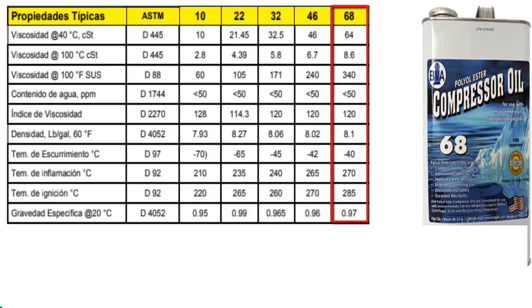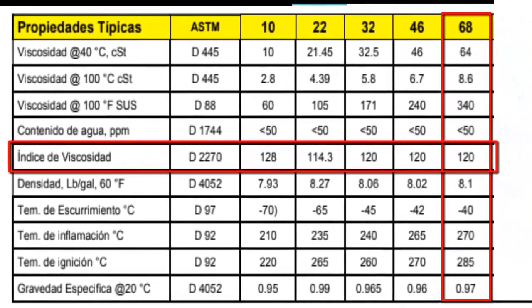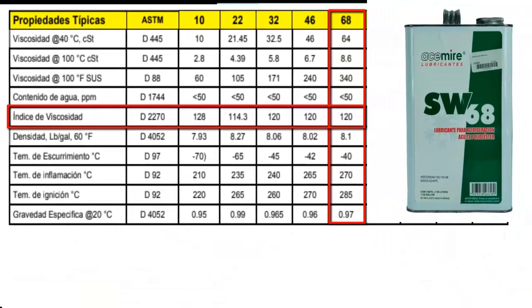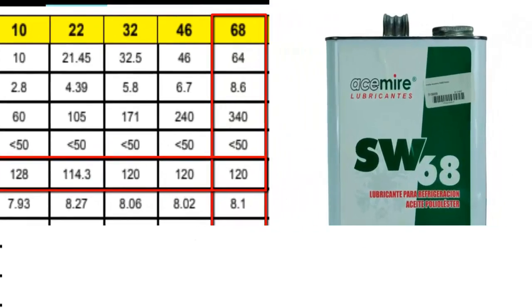The viscosity stability index is a numerical measure that describes how the viscosity of a lubricating oil varies with changes in temperature. When a lubricating oil has a viscosity index of 100, it is considered to have very stable viscosity over a wide range of temperatures. As the viscosity index decreases below 100, it indicates that the oil's viscosity tends to change more significantly with temperature variations. In this case, according to the table, this POE-68 oil has a viscosity index of 120. So we can conclude that POE-68 oil not only has the perfect viscosity, but also has the capacity to stabilize this viscosity value.